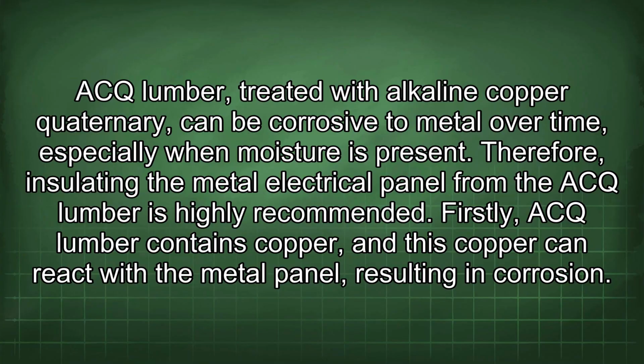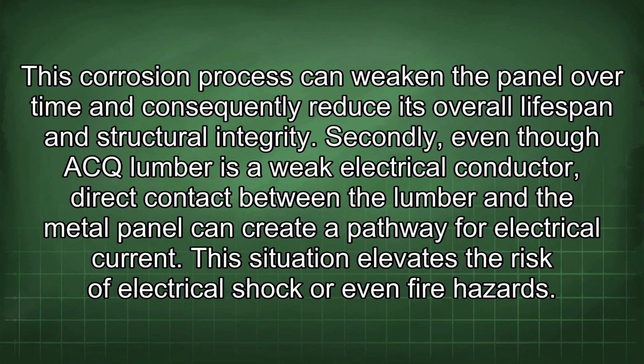ACQ lumber, treated with alkaline copper quaternary, can be corrosive to metal over time, especially when moisture is present. Therefore, insulating the metal electrical panel from the ACQ lumber is highly recommended. Firstly, ACQ lumber contains copper, and this copper can react with the metal panel, resulting in corrosion. This corrosion process can weaken the panel over time and consequently reduce its overall lifespan and structural integrity.